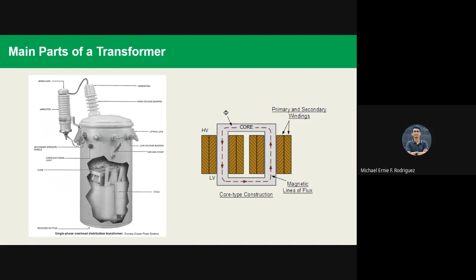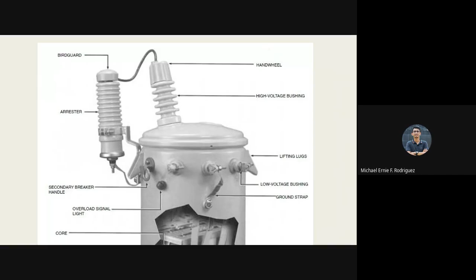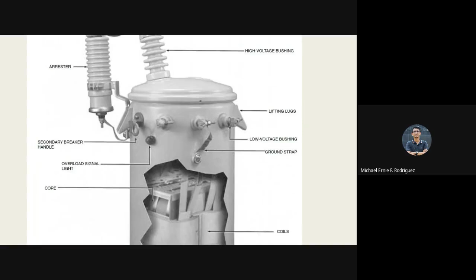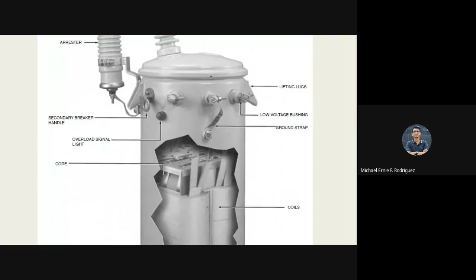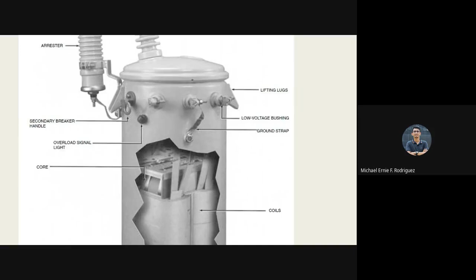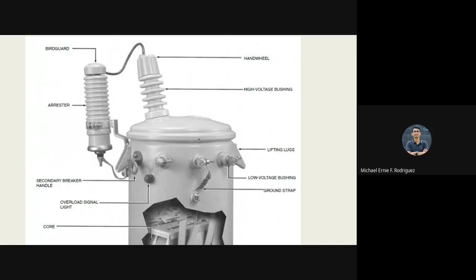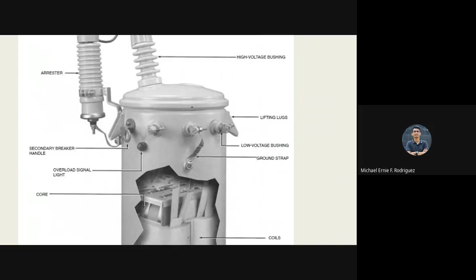You have the high voltage bushings, and with it a surge arrestor already installed. There's a bird guard, lifting lugs, a secondary breaker handle, and this transformer has an overload light signal that lights up when there's an overload. There's a ground strap, a low voltage bushing, and a high voltage bushing where the high voltage connects, say 7.62 kilovolts, and the low voltage side, which is 240 volts, connects there.